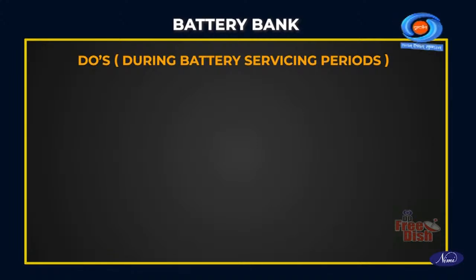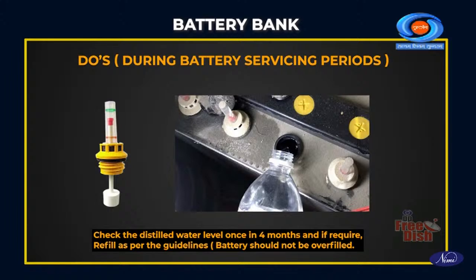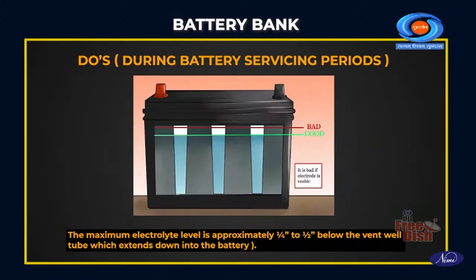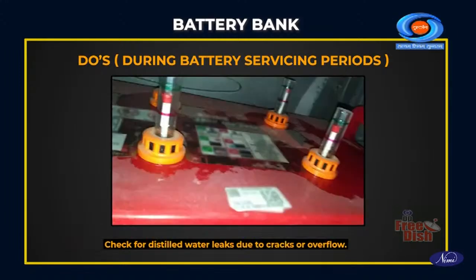Do's. During battery servicing periods, check the distilled water level once in 4 months and, if required, refill as per the guidelines. The battery shouldn't be overfilled. The maximum electrolyte level is approximately 1/4 to half inch below the vent well tube, which extends down into the battery. Check for distilled water leaks due to cracks or overflow.